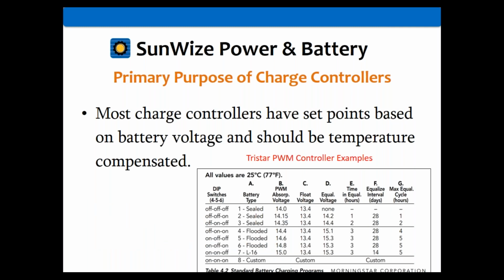Most controllers will have set points based on the battery voltage, and that should be temperature compensated. Temperature compensation and having the right set points are needed to make certain the algorithm for your battery is correct.